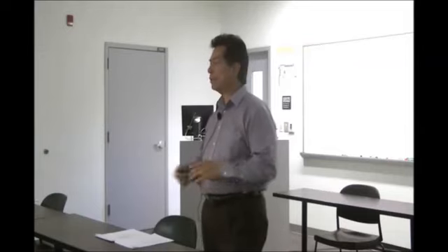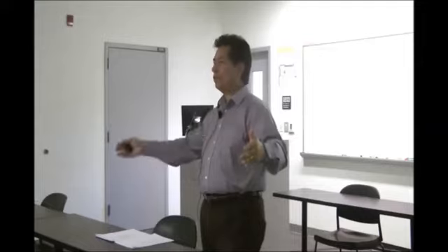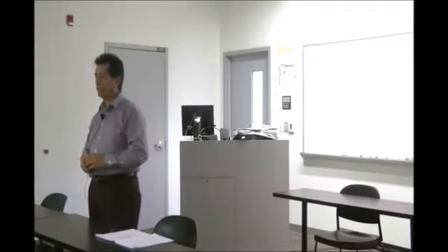Say I got a 20-story high-rise, right? Typical work days are Monday through Friday. I got a tenant that moves in, and their work week is now Tuesday to Saturday, and guess what floor they're on? They're in the middle floor. My controls support 3 floors at a time, which means I'm cooling 2 additional floors for this tenant on a Saturday.